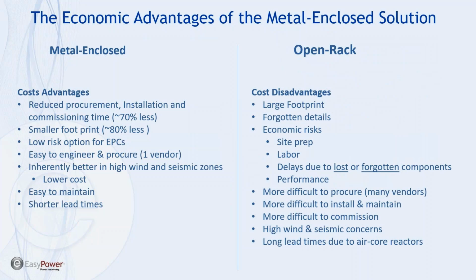The metal enclosed system is easier to engineer and procure. We have one vendor. What's key with metal enclosed systems is that the responsibility of design and procurement and assembly goes to the metal enclosed supplier. Okay, the metal enclosed supplier is probably supplying between 100 and 300 systems a year. For an EPC to develop a harmonic filter system using an open air solution, the engineer involved with that project might be designing a harmonic filter for his first time, or maybe he only does one or two a year. So just from an engineering standpoint, metal enclosed solutions basically eliminate engineering costs from the project.